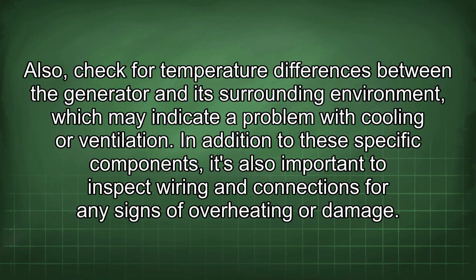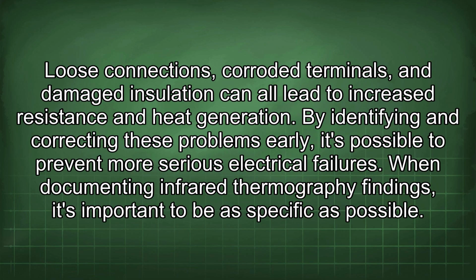In addition to these specific components, it's also important to inspect wiring and connections for any signs of overheating or damage. Loose connections, corroded terminals, and damaged insulation can all lead to increased resistance and heat generation. By identifying and correcting these problems early, it's possible to prevent more serious electrical failures.